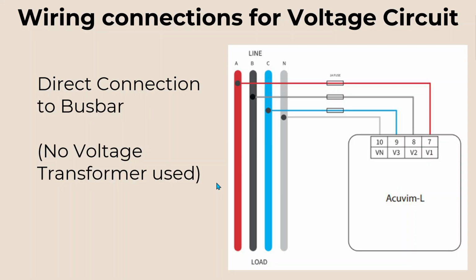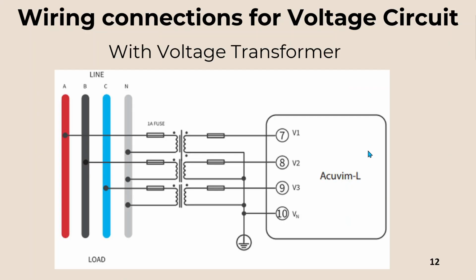For the voltage measurement and wiring, there is direct-to-bus-bar connection. It means you are not using a voltage transformer. As you can see in the diagram, the meter is directly connected to the bus bars through the protection fuses. This is another way to connect the voltage input of the meter to the bus bars, using a voltage transformer with fuse protection in both the primary and secondary of the transformer. In this case, you have to program the meter based on the actual ratio of this transformer. For example, if this is 480 volts and here it is 120 volts, the ratio should be programmed in the meter during configuration, which will be shown later.